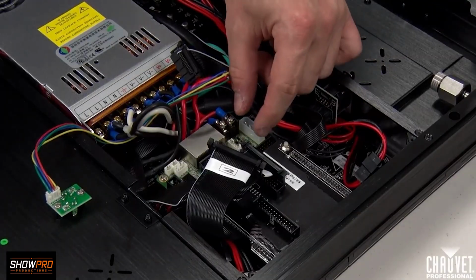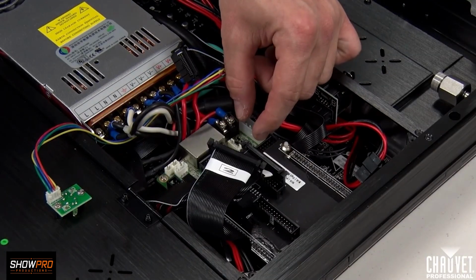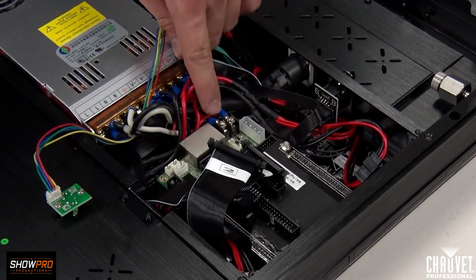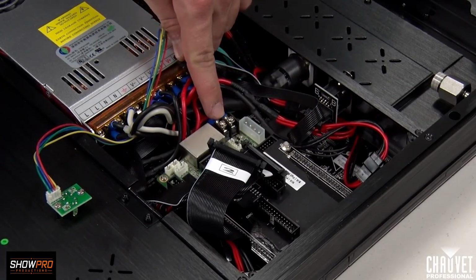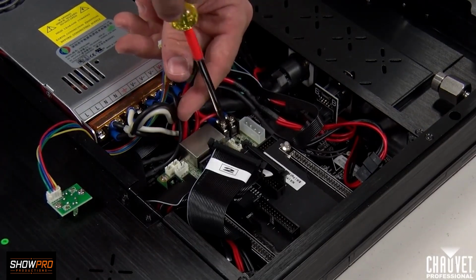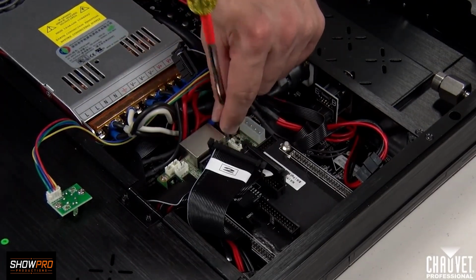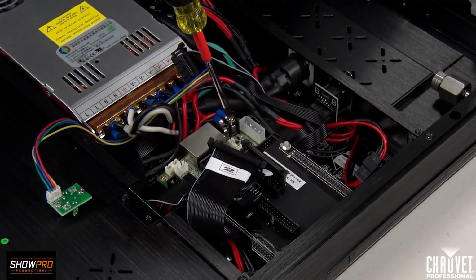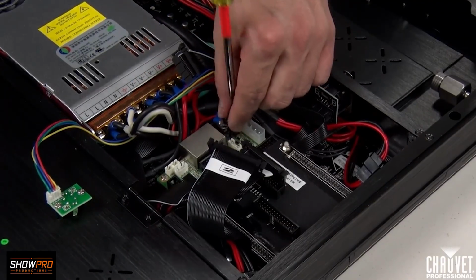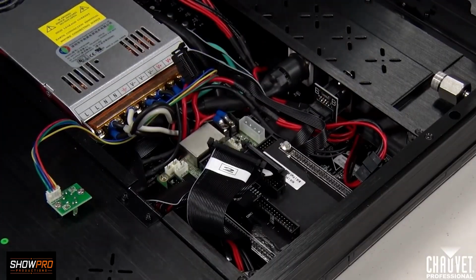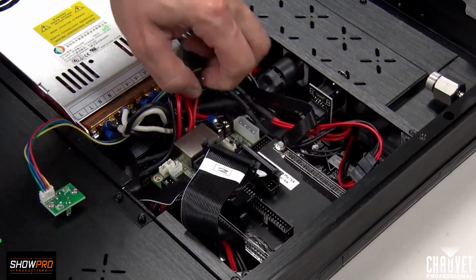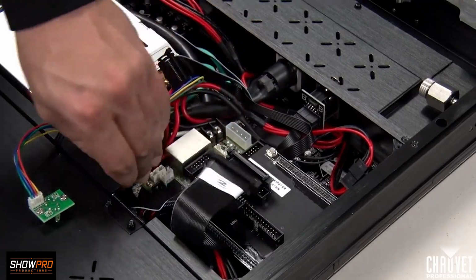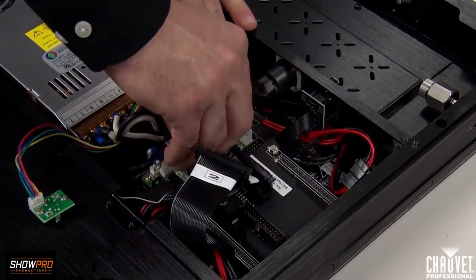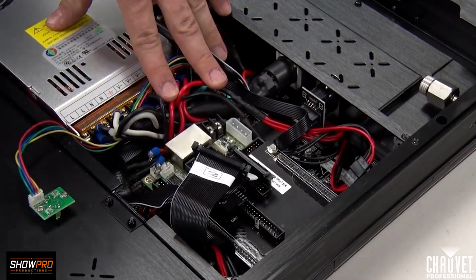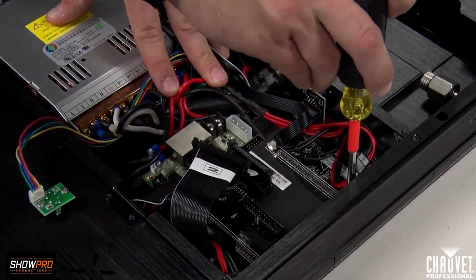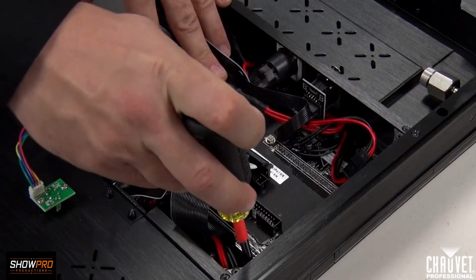If you find it difficult after removing the center screw to pull the control card out, your next option is to remove the 2 wires for the power input. Grab the wires, pull them out of your way. You may need to use a screwdriver shaft to pry from the back to remove them from the notch.